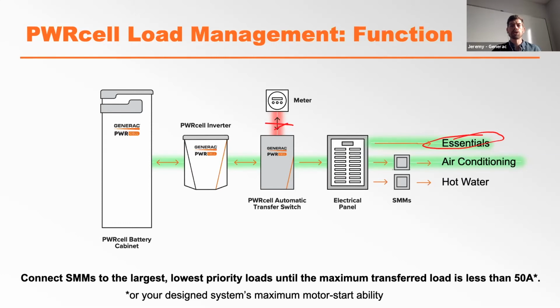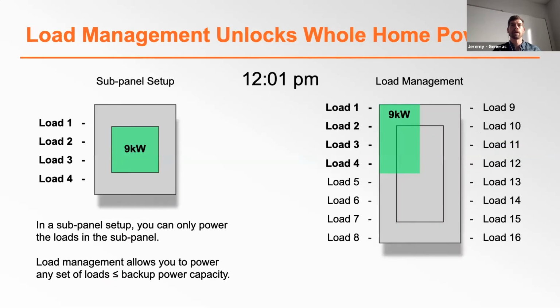Non-essential loads are going to share the balance of power available and may have to take turns cycling depending on how much power is available. If you're paying attention, I think you would have seen the hot water being on, then turning off, and the AC unit turning on because it's going to be a higher priority than the hot water heater here. The SMMs, our smart management modules, automatically control these managed loads, pausing them to yield power to higher priority loads. We'll take a look at this functionality in greater depth shortly. Let's see. Oh, there we go. There's the air conditioning turning off, the hot water heater getting power now that's available.